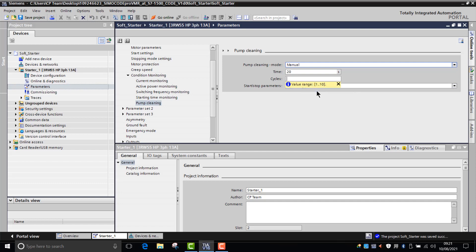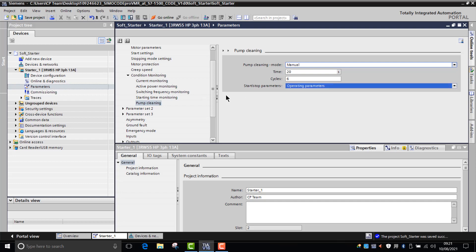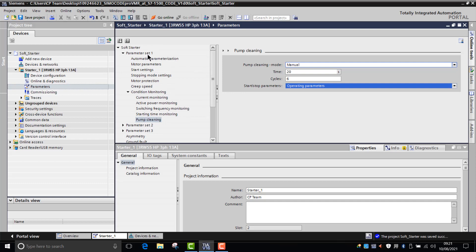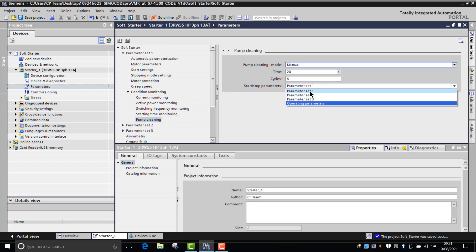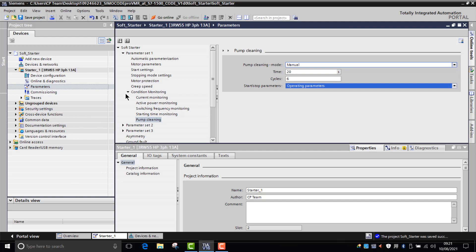Then you can decide which parameter set you want the pump cleaning function to operate in. You can choose operating parameters, which means it'll configure itself in parameter set one. You can also choose parameter set two or parameter set three, but for normal circumstances you just leave that as being operating parameters. Once you've done that, then you'd need an initiation mode.